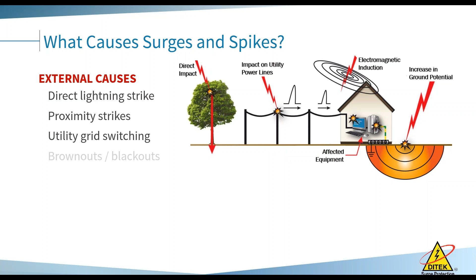Now let's look at what causes surges and spikes. A lot of people associate surge protection with direct lightning strikes, but we do not protect from a direct lightning strike, I can't stress that enough. I've personally worked with a couple of large commercial insurance carriers over the last 15 years, and I've been called onto sites with extraordinarily large claims, asking how we'd prevent this in the future. We even have insurance companies that will pay up to $25,000 proactively for surge protection to protect certain properties. What we're really trying to protect from are proximity strikes, ones that hit maybe a couple of streets over, up to 2 or 3 miles away, depending on soil conditions and the atmosphere. You also have utility grid switching, brownouts, and blackouts.